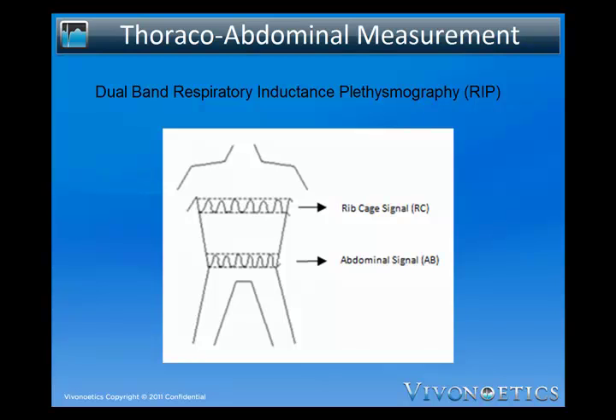A RIP sensor consists of a sinusoidal arrangement of electrical wires embedded in elastic cotton bands. A high frequency, low voltage oscillating current is passed through the wires to generate a magnetic field needed to measure the self-inductance of the coils, which is proportional to the cross-sectional area surrounded by the band. No electrical currents are passed through the body. This measures the approximate amount of air moved by the respiratory system by measuring the expansion and contraction of both the rib cage and the abdominal compartments.